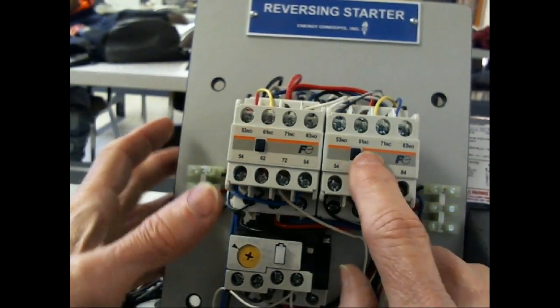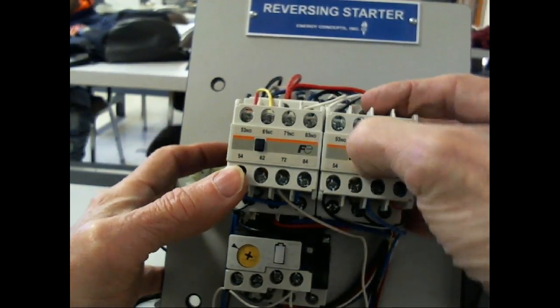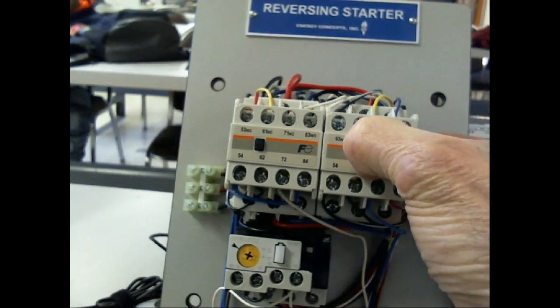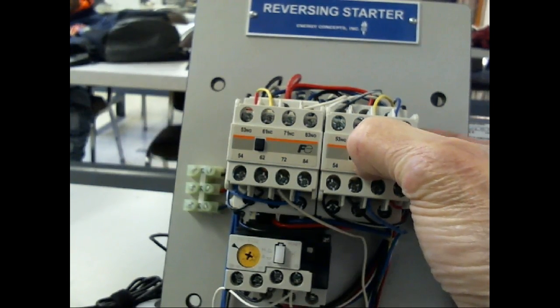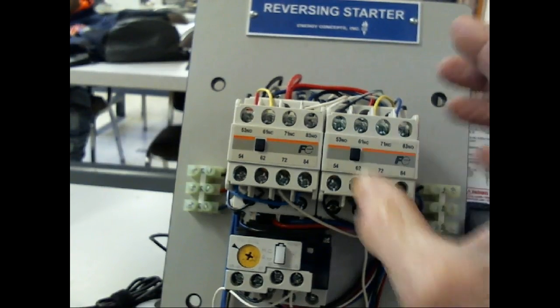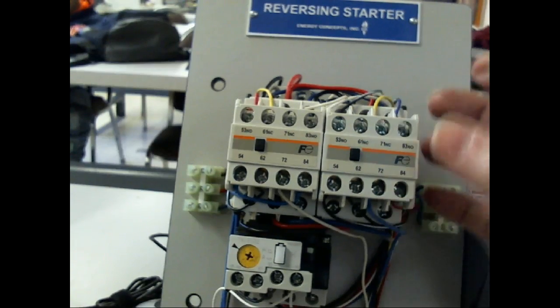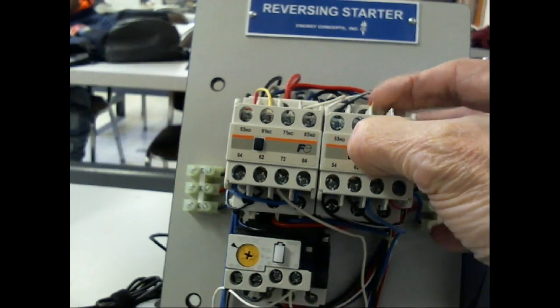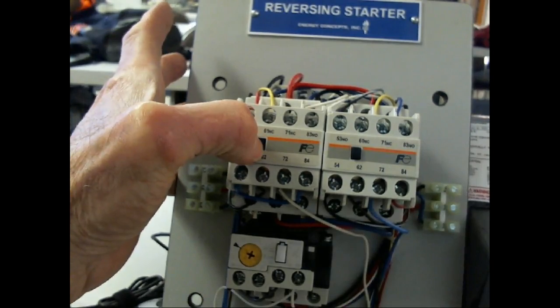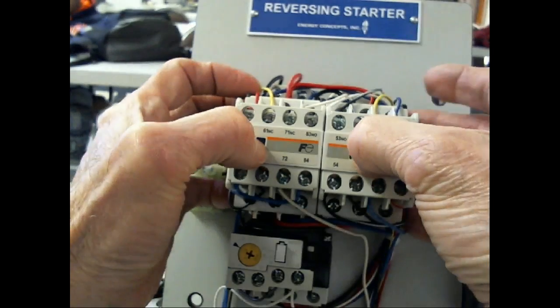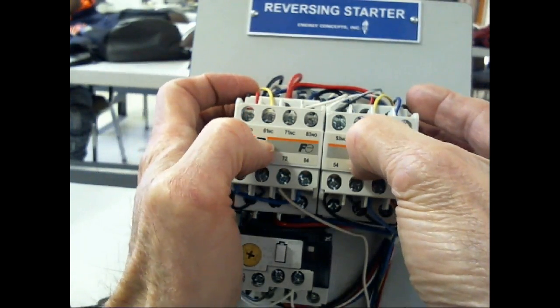Now these are push to test. So I can literally take this little black thing and push it in, and that would close the main power contacts on this one. It also closes the auxiliary contacts, but it closes the main power contacts on this relay. And if I press this one, it would do it on that one. But if I came over and did this, I just screwed up, right? You understand what I just did?